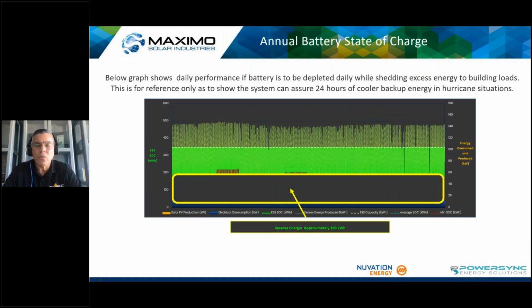And one of the requirements is that the battery never depletes below the 24-hour state. Since we had the load and we know exactly how much power it will consume through 24 hours, the system will be able to add excess power to the building and reduce the building loads, but we will always keep a minimum kilowatt-hour amount. That makes sure that if the system fails for any reason, if the PV panels get disconnected, or if all the building generators are off, you're still going to have at least 24 hours of building power. Next slide.